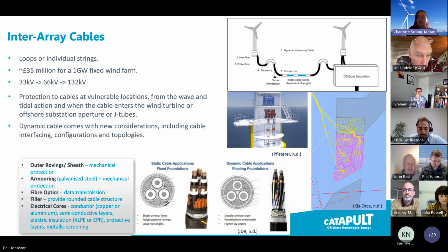All cable systems require protection. Dynamic cable protection will be different from static cable protection, but all protection is used to protect cables at vulnerable locations. This can be protecting them from wave and tidal action, where the cable enters the wind turbine or the offshore substation, J-tubes, and substructure interfacing. Dynamic cables come with new considerations, including designs for cable interfacing, your buoyancy modules, which are new for dynamic systems, new configurations and topology designs. Some of these topologies are optimized to improve O&M. These will include connectors that could either be at the substructure or on the seabed. They could be two-way connectors or they could be subsea hubs. It also sees the introduction of multiple armored layers on your cable, as well as dynamically treated cores. Next slide, please, Phil.